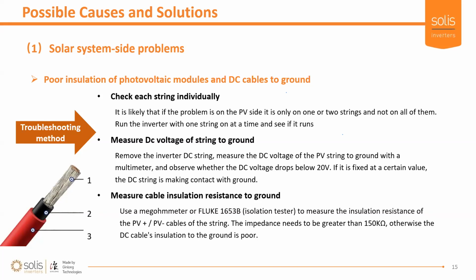Also on rainy days, the water could get into this new gap, this new hole, and cause a lower resistance to earth. I've also found that water buildup in MC4 connectors can cause these faults. I've had a couple of systems where I've had calls, and we've investigated using methods I'm going to show you now. We found out which string it was, and which pole of that string it was on. And then it turned out it was just an MC4 connector. So yeah, water and moss buildup in the MC4 connector. Replaced the MC4 connector and everything was good.